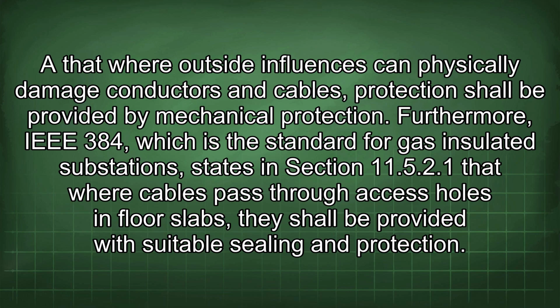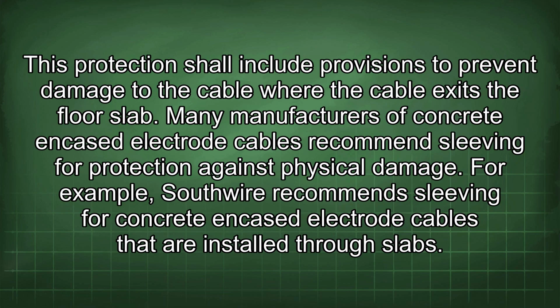Furthermore, IEEE 384, which is the standard for gas-insulated substations, states in section 11.5.2.1 that where cables pass through access holes in floor slabs, they shall be provided with suitable sealing and protection. This protection shall include provisions to prevent damage to the cable where the cable exits the floor slab. Many manufacturers of concrete encased electrode cables recommend sleeving for protection against physical damage. For example, Southwire recommends sleeving for concrete encased electrode cables that are installed through slabs.